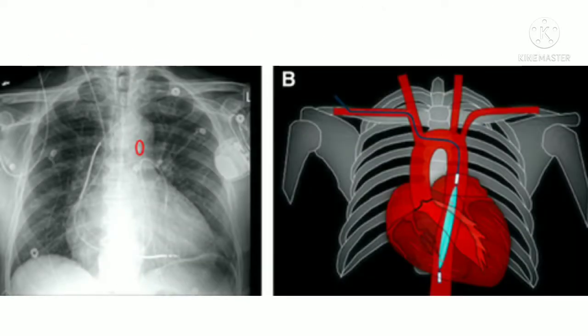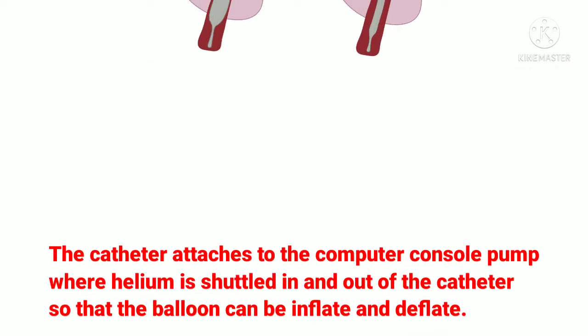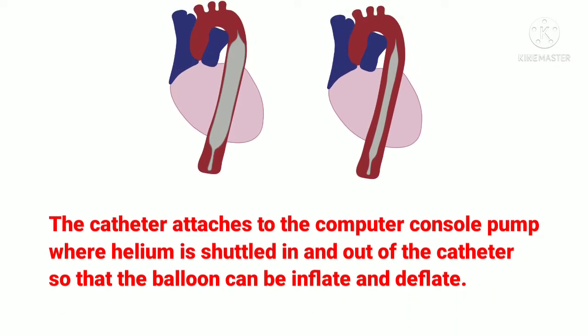The catheter tip is radio-opaque, so its position can be visualized on X-ray film. The catheter is attached to the computer console pump where helium is shuttled in and out of the catheter so that the balloon can be inflated and deflated.